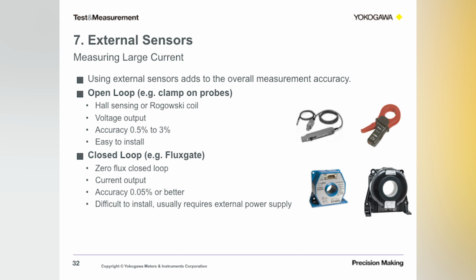Right? There are two types of current sensors. One is the open loop type. These are typically the clamp-on type probes like Hall sensing and Rogowski coils. They usually have a voltage output, which is susceptible to noise, and a typical accuracy of 0.5% to 3%. So if you're looking for real accuracy in your measurements, sometimes these are not good. You need to use something more accurate. But they are easy to install, as you can see. They're easy to clamp around the wires you want to measure current on, and in certain conditions where that accuracy is acceptable, you will end up using open loop type external sensors.